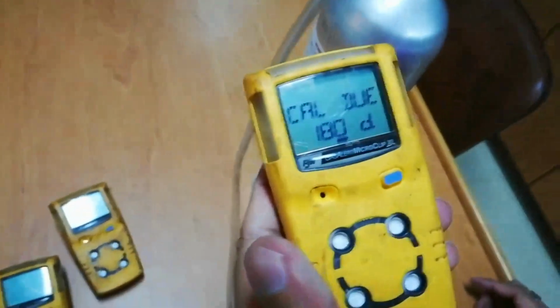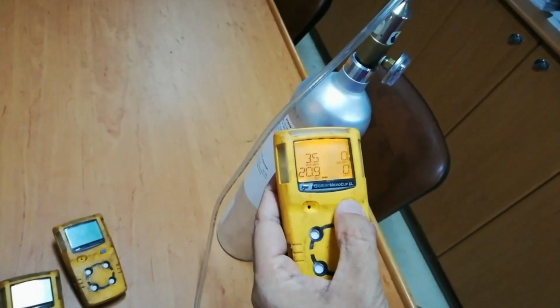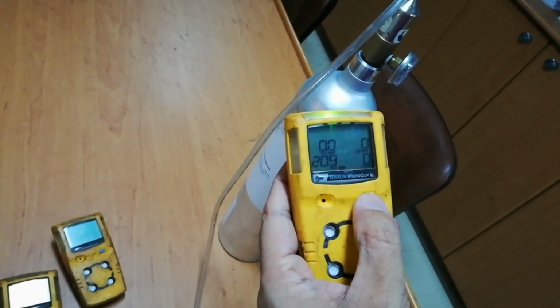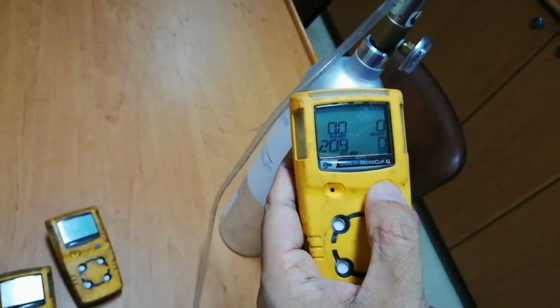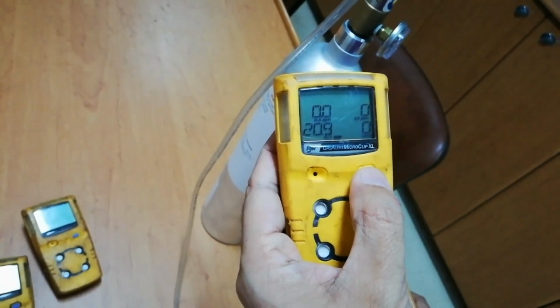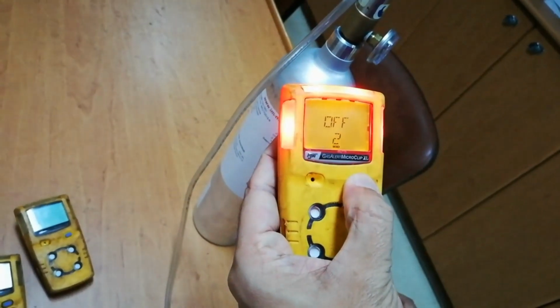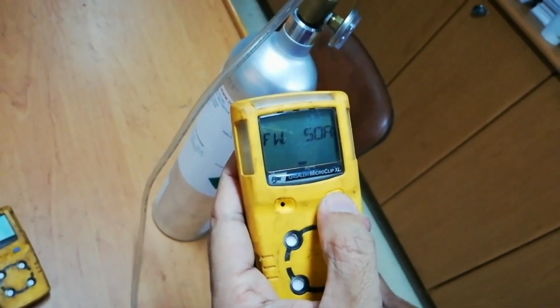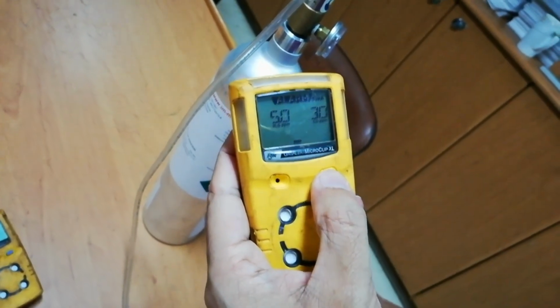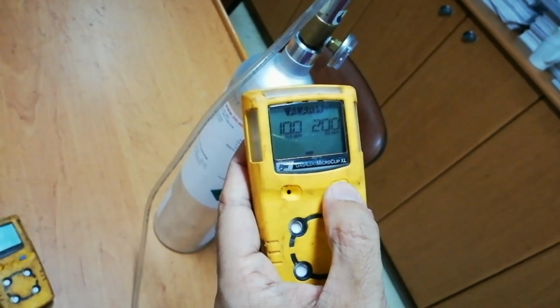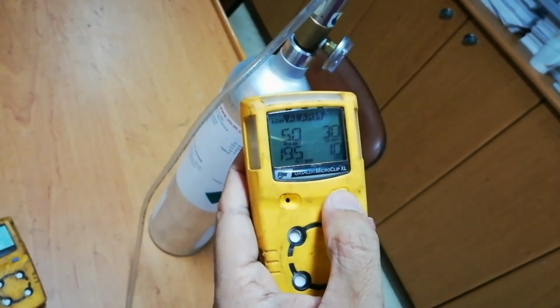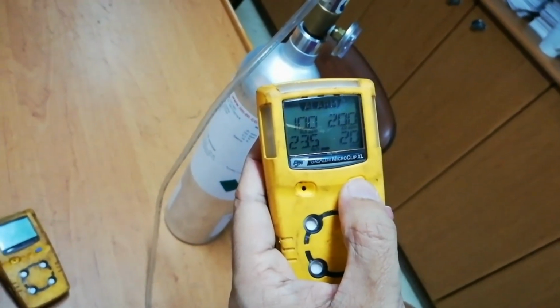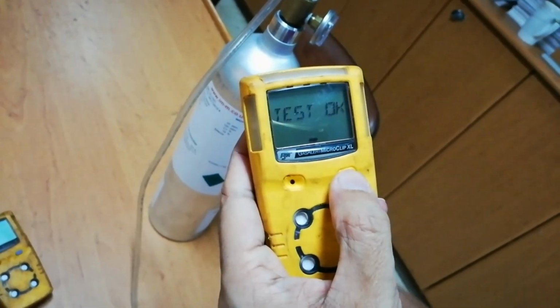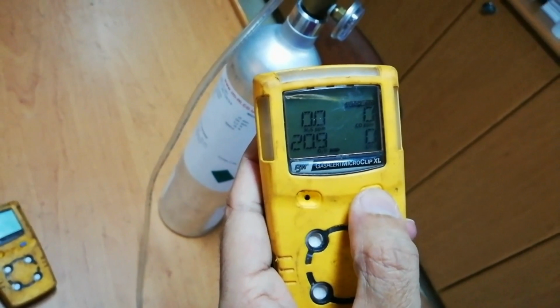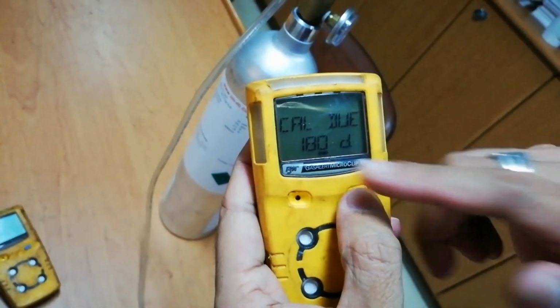You see the calibration is now already done, and again we are going to switch off this multi-gas detector, and we can cross-check whether the calibration is done or not. Okay, I am going to switch off. Okay, switch on again, and here you can see it will start the self test first, and once the self test is completed it will show how many days are remaining for the calibration. It should be 180. Okay, self testing, test okay, and it will show calibration due in 180 days.